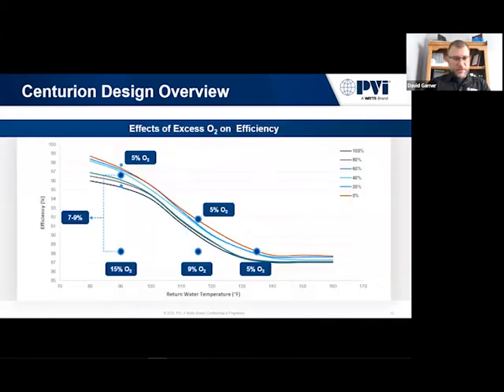And if we take our standard efficiency curves, which I believe everyone's very familiar with, what happens with those increased levels of O2 is you actually change the dew point of the natural gas. So instead of condensing at that 135, give or take, point, and that's where you always see the spike in the efficiency curve, if our O2 levels start increasing to 9%, 15%, this is where the dew point starts to level out. Let's say we're at 15% O2, return water temperature at 90 degrees, we're not condensing. We're operating at about 87, 88% efficient at best, just because the O2 is out of whack.